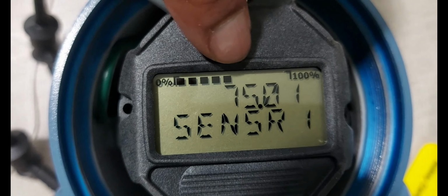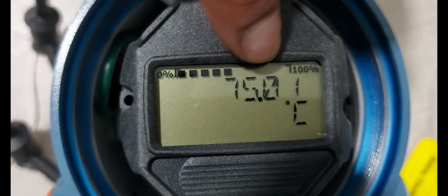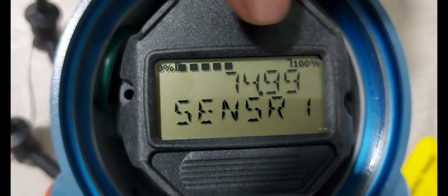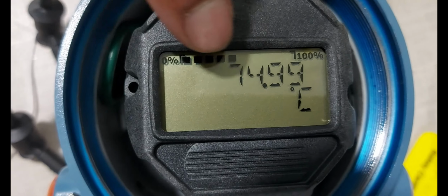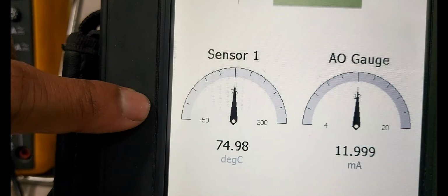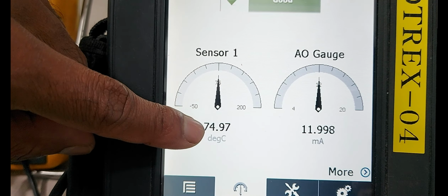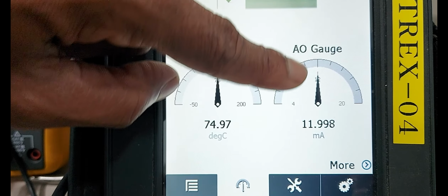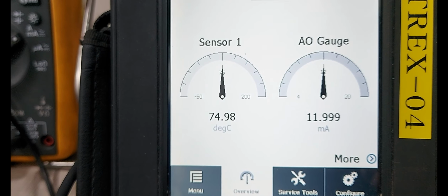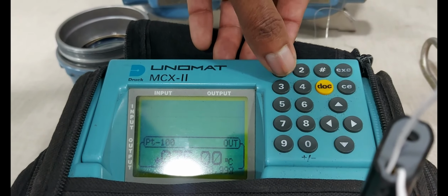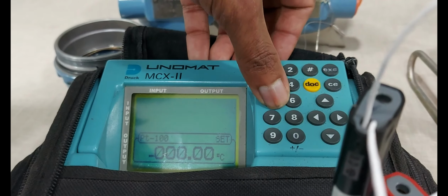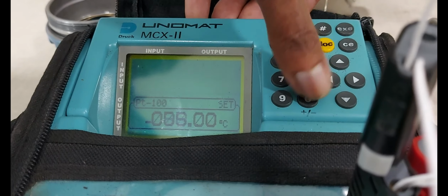Transmitter display showing 75.01 degree. Sensor 1 only. Sensor 1 temperature 74.97 and the output value is 11.998 milliamps. Next we are applying minus 50 degree, zero value, minus 50 degree.